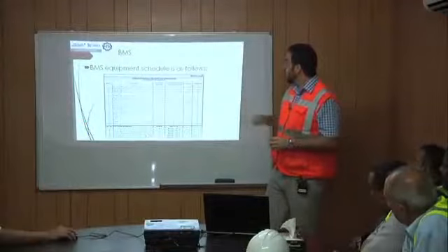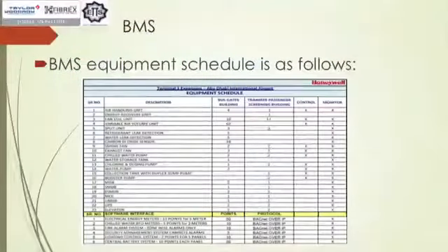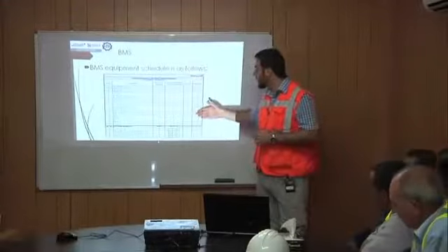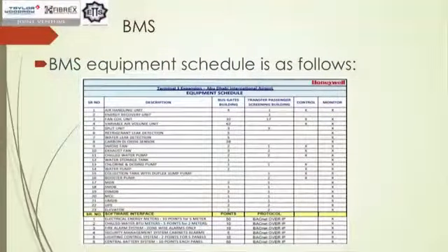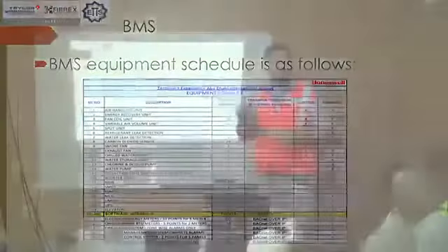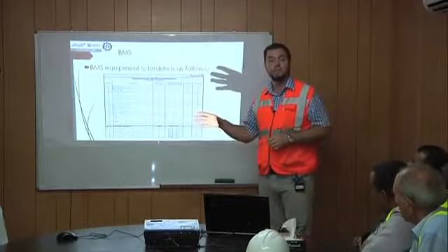Okay, components. Our BMS is handling the air handling units. It's controlling the fans. Here we're showing which items are actually controlled and which items are monitored. If we're mentioning that it's controlled, that means you can go through your graphical representation, you can click on the unit, you can activate this damper, you can increase the voltage of this fan, you can decrease the voltage of that fan. All of this is integrated.